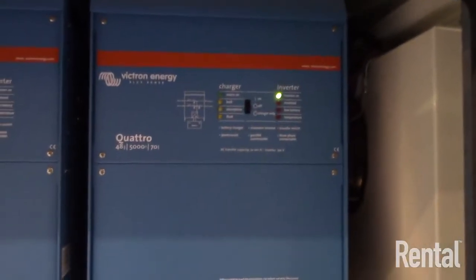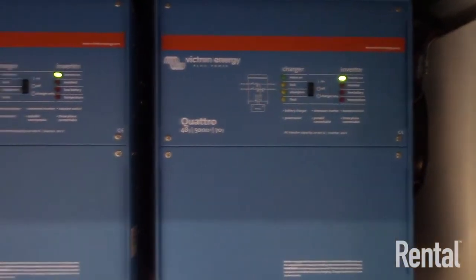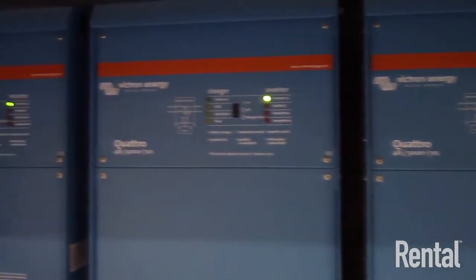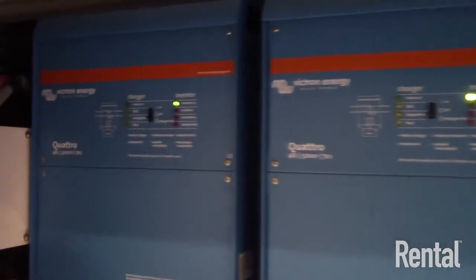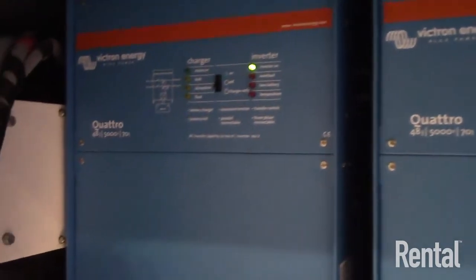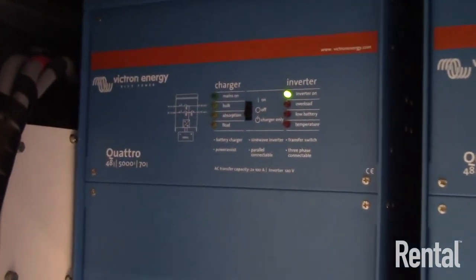Tower cranes and construction site elevators are another good application, because the generator has to be sized based on the crane lifting its maximum load and slewing at the same time. That results in the generator being sized in a worst case scenario, so it's often very oversized for the job. By implementing the hybrid power system, we can actually either downsize the generator or let the generator run for less hours in the day.